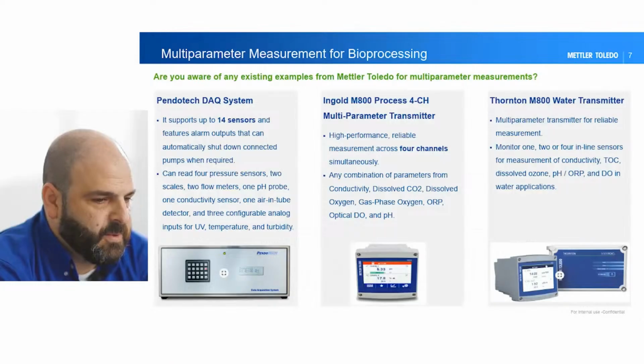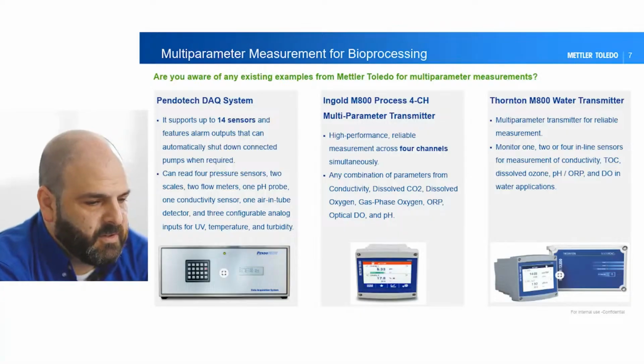Within Mettler-Toledo's portfolio, multi-parameter measurement solutions exemplify this approach. For example, the Pendotech DAQ system supports up to 14 sensors and includes alarm outputs capable of automatically shutting down connected pumps when necessary. It can monitor an array of inputs, including pressure, weight, flow, pH, conductivity, UV, turbidity, and temperature.